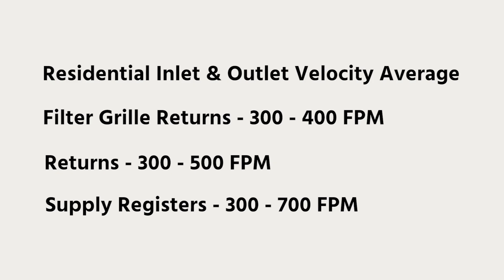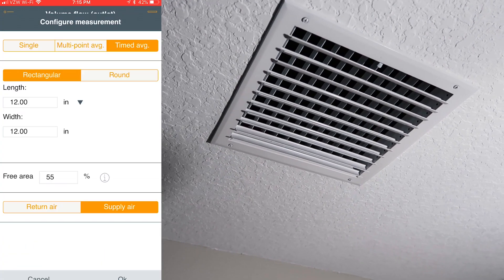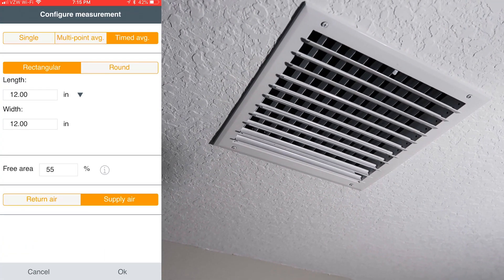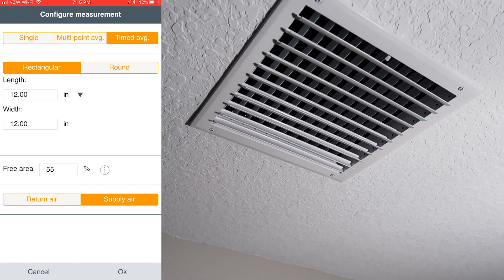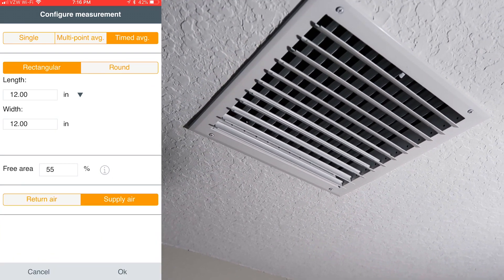In general, in a residential air conditioning supply duct, we want to see velocities anywhere from 300 feet per minute to about 700 feet per minute. I've intentionally set really low velocities for the purpose of having low air noise. I'm going to be doing a timed average traverse. You can see I've got it already set in a 12-inch by 12-inch, 55% free area — that is off the specs for this actual vent. You have to look carefully at the specifications for the vents in order to find that.